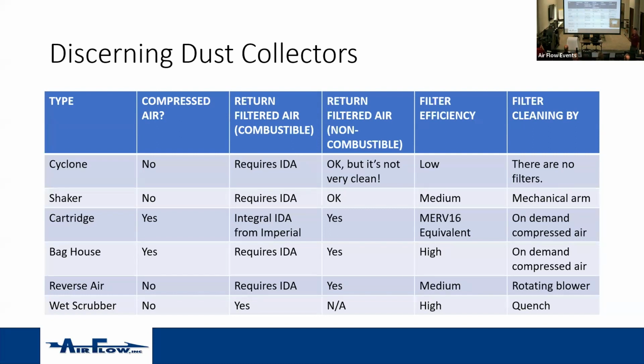You can definitely return air directly out of a cyclone, but your very fine, smaller micron dust is going to get picked up in that clean air side and put back into your building. So after filters are recommended. Filter efficiency, when you're looking at microns versus a MERV rating, through a cyclone is low. And the nice thing with a cyclone is very minimal moving parts and very minimal filter. There's no filters, nothing that needs to be replaced.